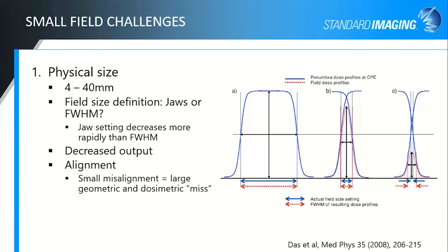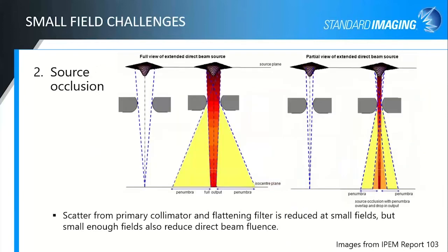The other thing that really matters, as I'm sure you're all aware, when you get down to these very small physical sizes for the fields, is alignment of your detectors. If you have a very small mismatch in a large field, it doesn't really affect your measurement too much, and so your uncertainty is pretty reasonable. In a very small field, your positioning uncertainty plays very heavily into your measurement uncertainty, because a very small misalignment can be a very large geometric or dosimetric miss or error.